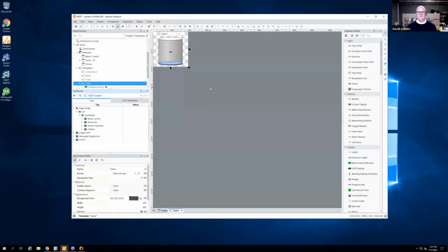And like you said, you're using the concepts from ISA 95 with that activity hub in the middle. Layers of the automation, data coming from certain layers, the activity hub being the unified namespace. That's where the data is going to go, and then it comes back out to another layer to the screens you're going to be creating in Ignition, right? Yeah, I have edge nodes publishing to the UNS, and then I have a SCADA and a historian node that are subscribing to that data based on the topics that are there.